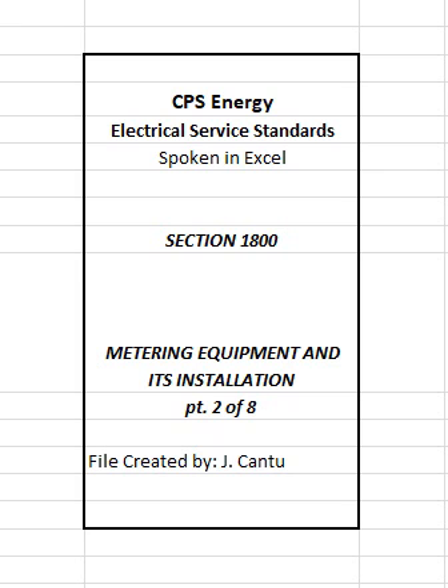H. For services supplied from the downtown network system, CT/VTs will either be installed within a CPS Energy furnished instrument transformer enclosure or may be installed within a compartment specifically designed and isolated for metering equipment in customer's switchgear or switchboard. Where CT/VTs are to be installed in an instrument transformer enclosure, the enclosure shall be installed by customer. Refer to section 1100.